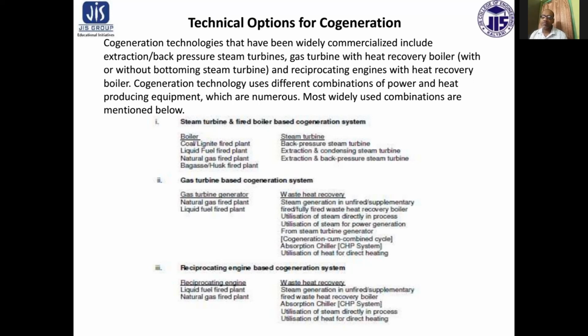Next is the gas turbine based cogeneration system. That is, it may be a natural gas fired plant or a liquid fuel fired plant. The waste heat recovery can be done by steam generation in an unfired or supplementary fired boiler, or a fully fired waste heat recovery boiler. It may be utilization of steam directly in the process, or utilization of steam for power generation from a steam turbine generator. That is cogeneration cum combined cycle. And there is absorption chiller, and utilization of heat for direct heating.